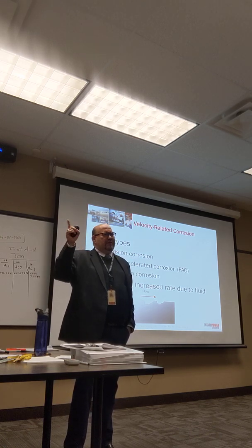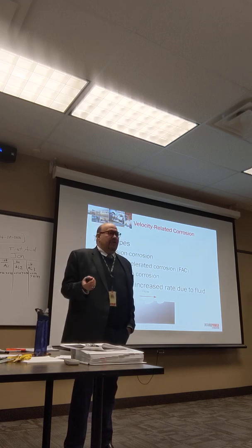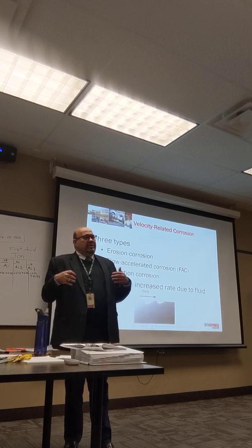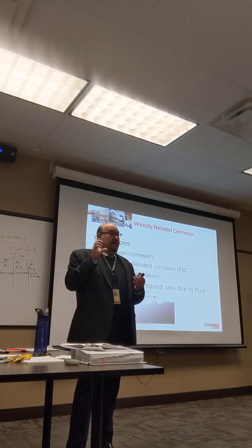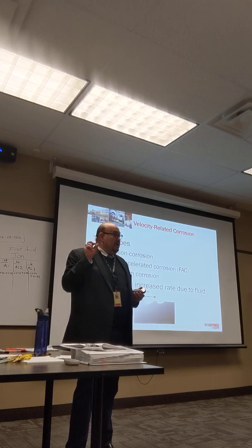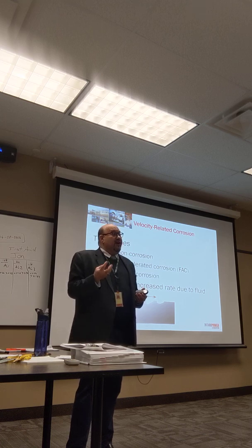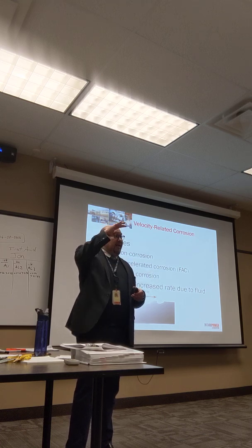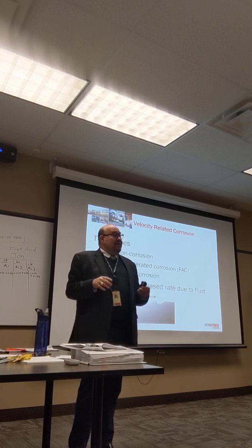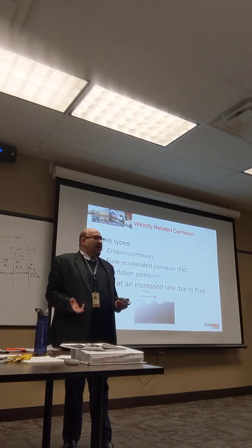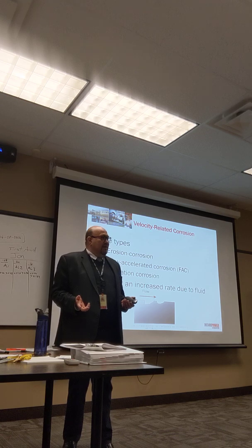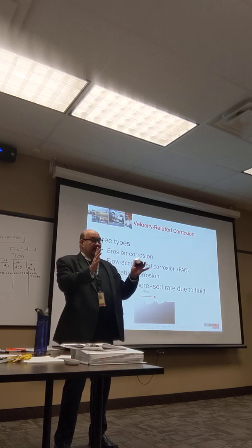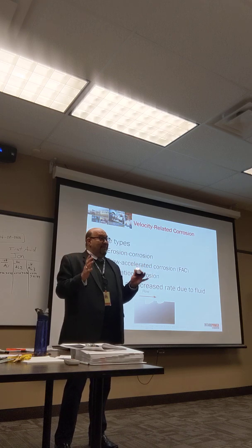We're having a lot of thinning in this area, and it turns out that as the PHT is departing the fuel channels, the outlet is very hungry because the temperature has been raised, and it's all zirconium, so it's not really picking up from the zirconium environment. It has the affinity. You've actually increased the size of its appetite.